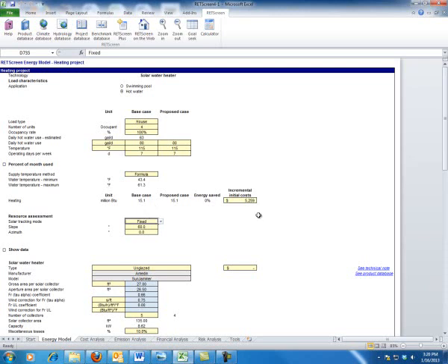We're going to fix this to the south. So that means this solar location is going to be pointed due south at a fixed axis, or fixed slope, I should say, of 60 degrees. The reason I chose 60 was that I wanted to do latitude plus 15 degrees. My location here is 40 degrees, plus 15 means I have 55 degrees. I wanted to go slightly higher, and the reason for it is I'm going to oversize my system just a touch and use a little bit of that heat to offload in my home.